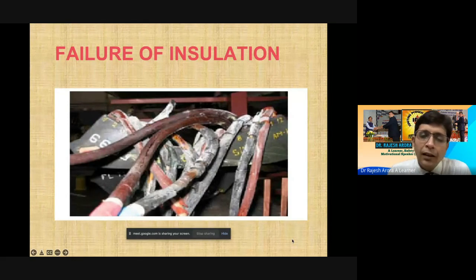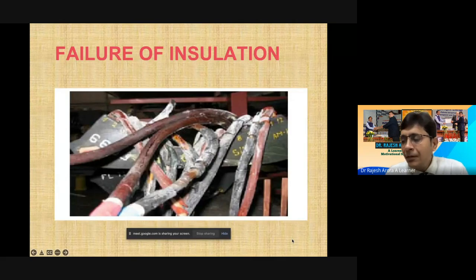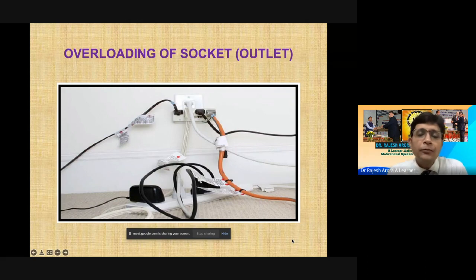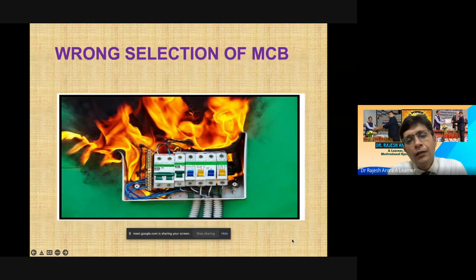Failure of insulation may be due to some error, faulty outlets, plugs, or use of wires under your carpets, which also sometimes become the cause of insulation failure. Be careful. Overloading of sockets is a very common scenario. We have to think about it. Selection of MCB: basically, there are three types of MCBs, and we have to choose our MCB based on our application: B, C, or D.